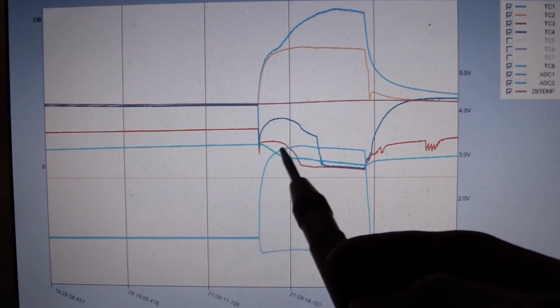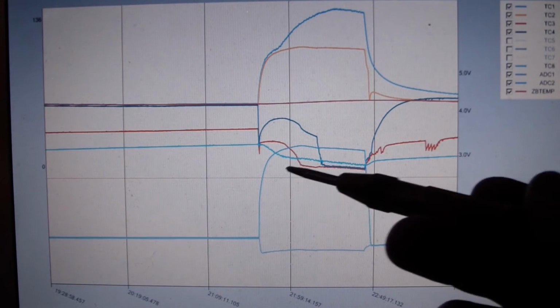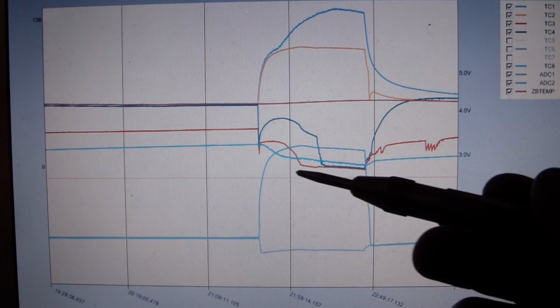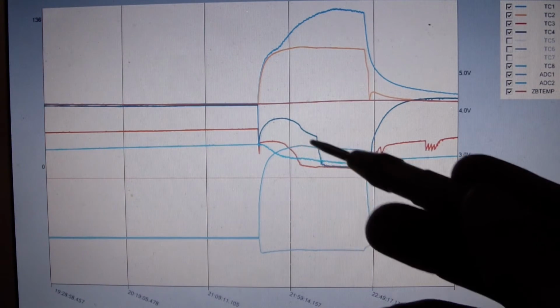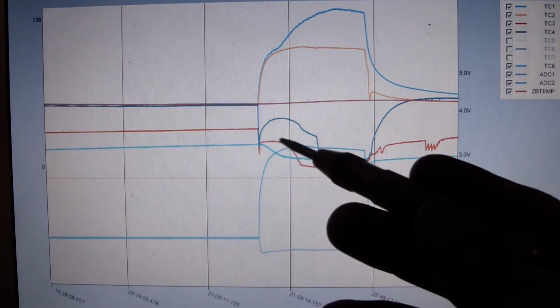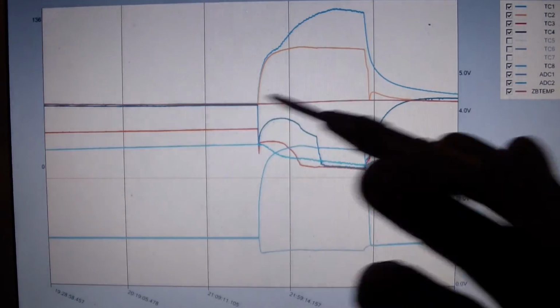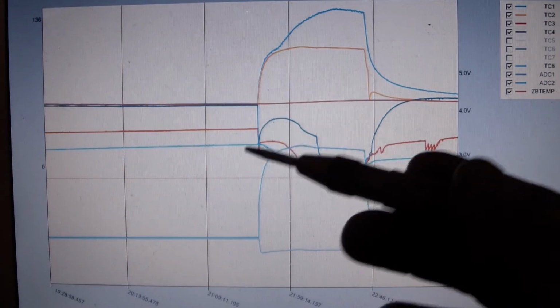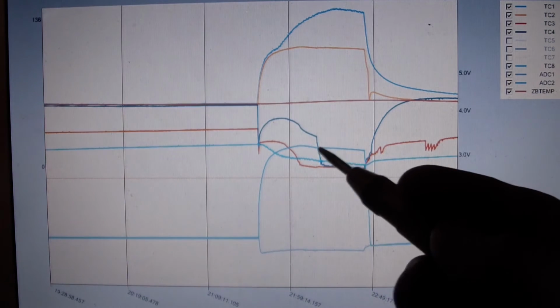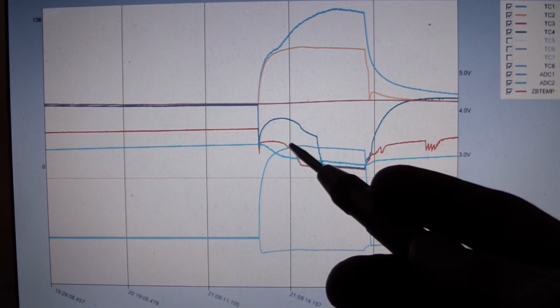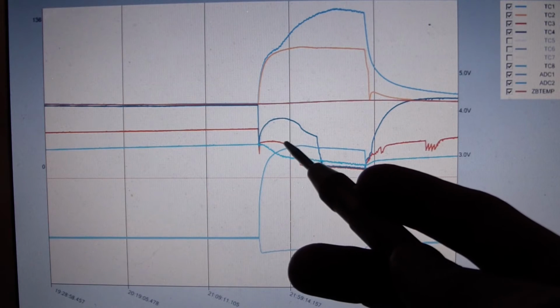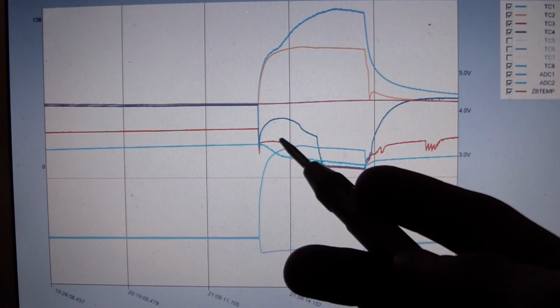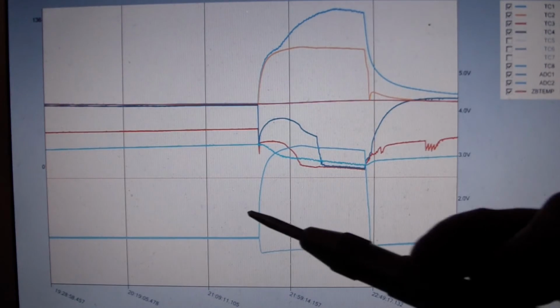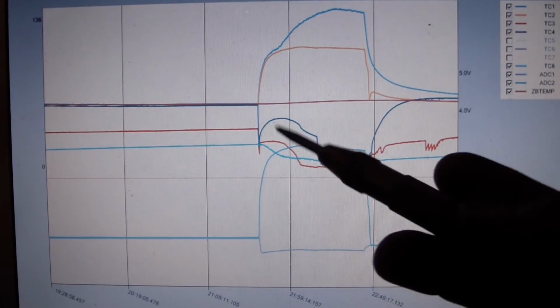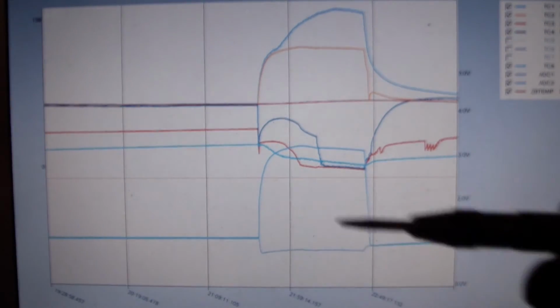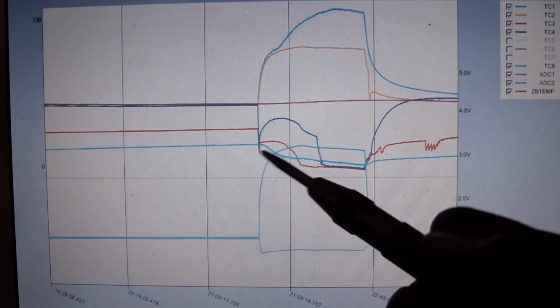The evaporator has a lot of work to do, and for a given mass flow rate entering the evaporator, it might not be sufficient to properly feed it. That's one of the reasons we're getting higher superheats on the suction line, apart from the warm gas passing from the capillary tube. But then, of course, over time, it is still doing some cooling. I mean, it's definitely dropping in temperature. There's no doubt about that.